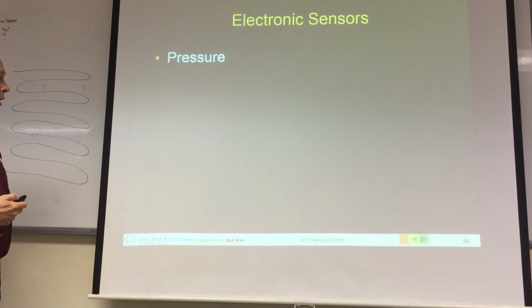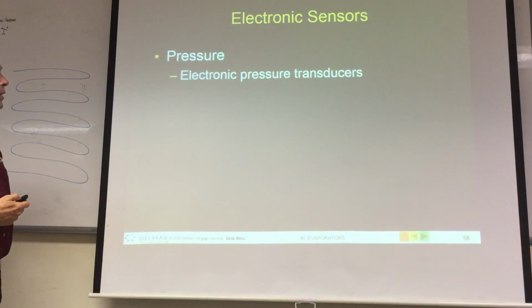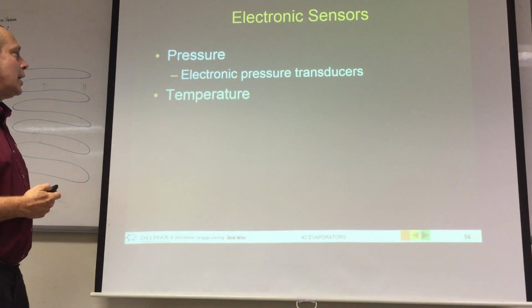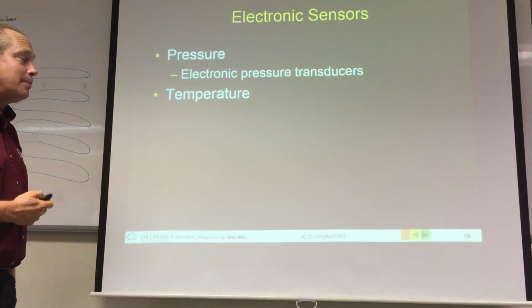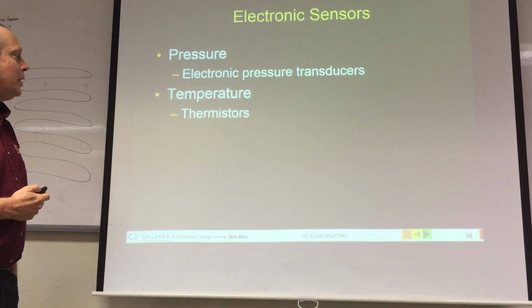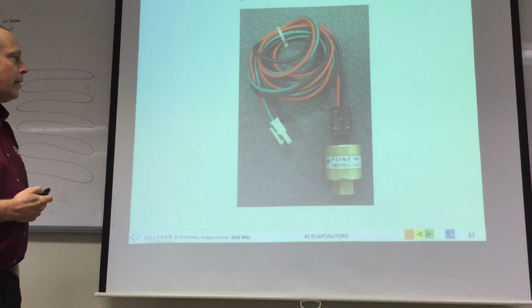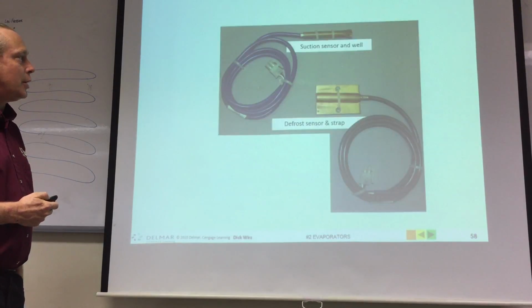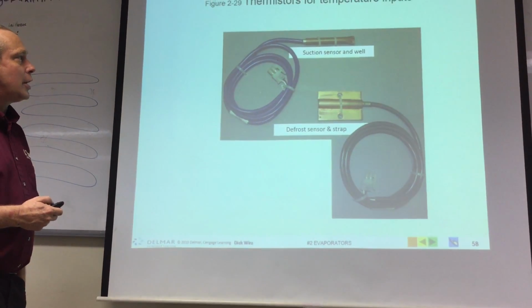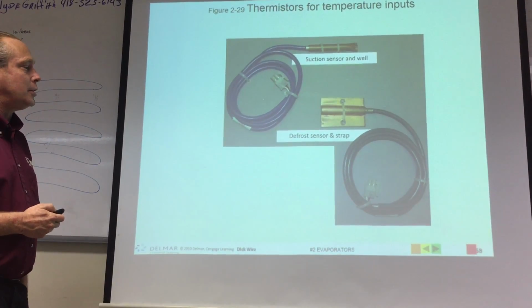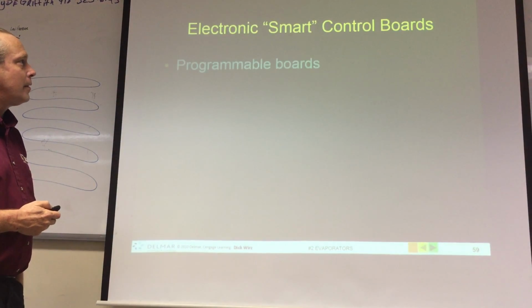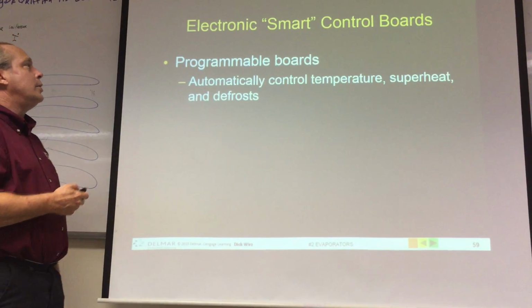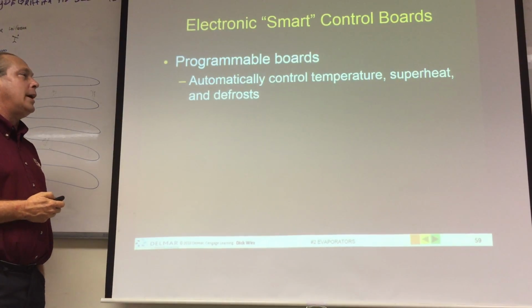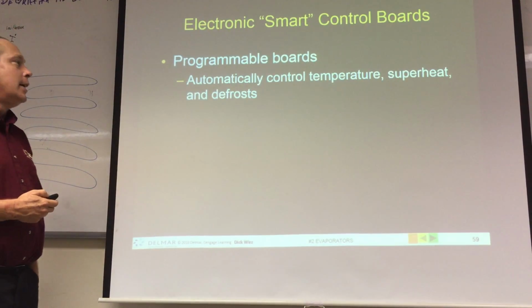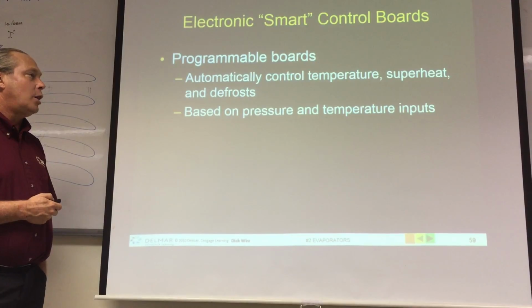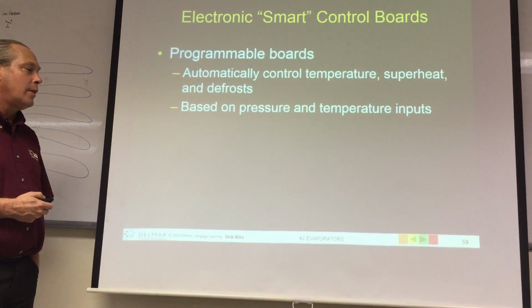And then we have electronic sensors. They sense pressure, electronic pressure transducers, temperature with thermistors. There we go. There's a pressure transducer. There's a couple of different temperature transducers. Programmable boards for these smart control boards, automatically control temperature, superheat, and defrost based on pressure and temperature inputs.